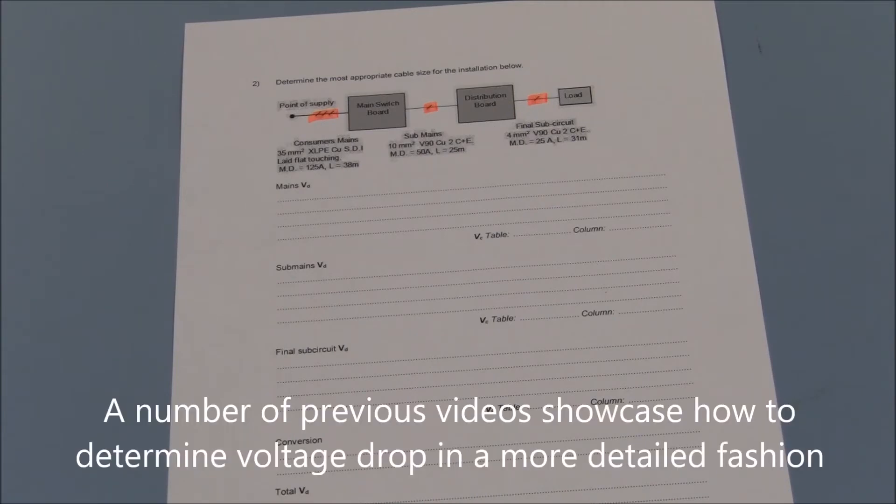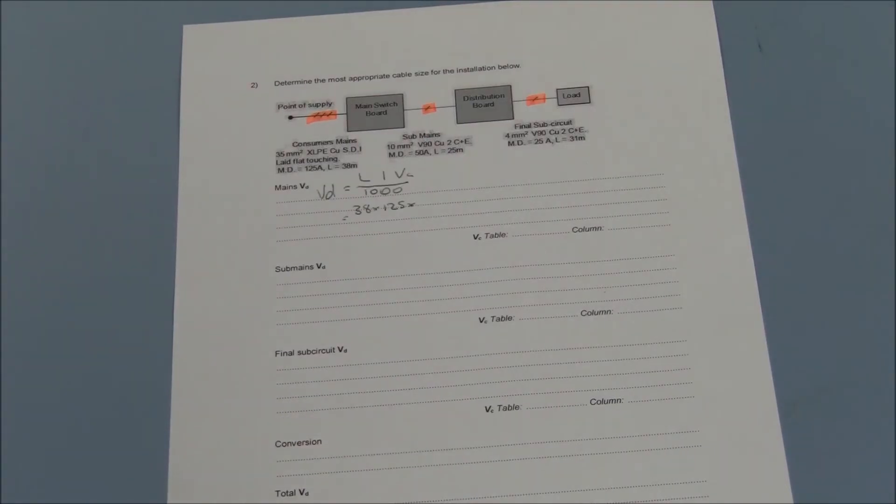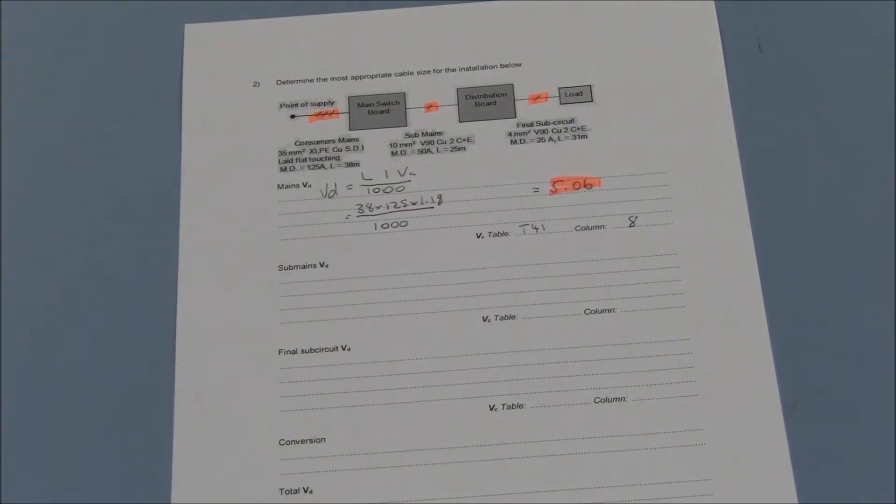Previous videos have detailed determining voltage drop of known cables, so we will move swiftly through the voltage drop of the consumers mains, landing on 5.06 volts courtesy of table 41 column 8.